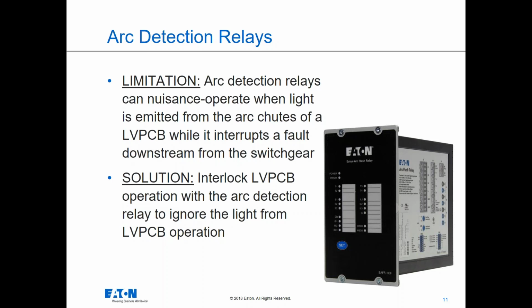There are also some design limitations that come with using light and combining it in a power circuit breaker scenario. When a power circuit breaker operates to actually interrupt a normal fault, it will puff some light and smoke into a circuit breaker cubicle just by action of doing its normal job. It could be just a standard overcurrent situation or a normal kind of fault interruption that's not an arc flash. And so if you have a light detection method in that cell, now you need to start iterating to a sensitivity that's appropriate for that breaker in that situation. So you may need to desensitize the light detection to accommodate the breaker's normal physical operation, and thereby not really getting the level of arc resistance or incident energy resistance that's desired.